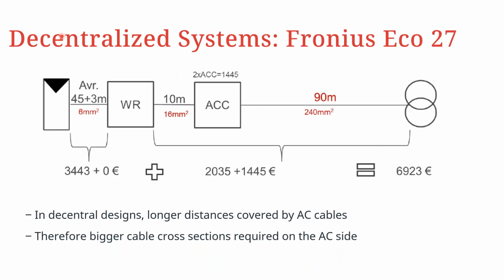Great. Going forward, we're now going to look at the decentralized system, starting with the Fronius Eco. As you can see, in this case the AC run is much longer than the DC run, so the AC component would be higher than the DC BOS component. Most notably, there are no DC combiner boxes, but the summation gives us about 6,923 euros.